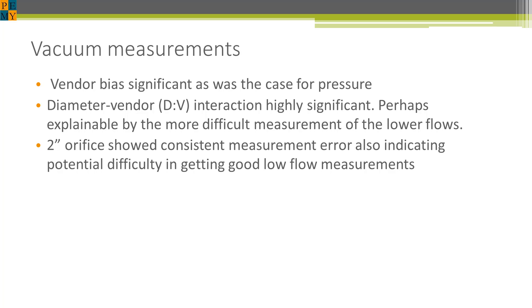First, the diameter vendor interaction was highly significant here, whereas it was not under the pressure mode. This most likely has to do with the measuring apparatus or the way the measurements were made. There was also a systematic type error in the measurement of the 2-inch orifice that also probably has to do with the inability to get good measurements at the small orifice flows.